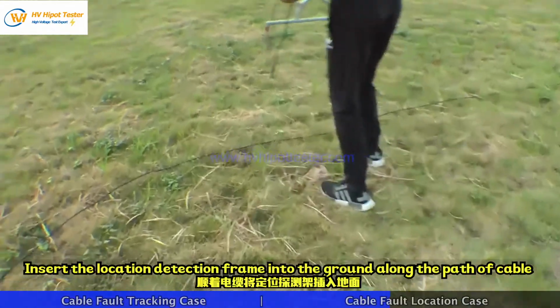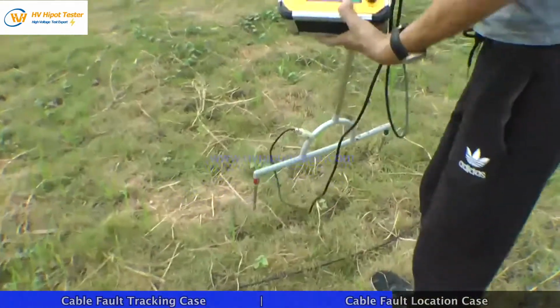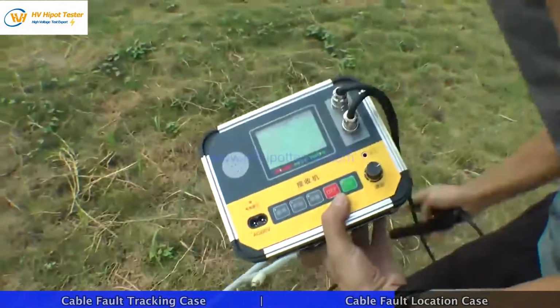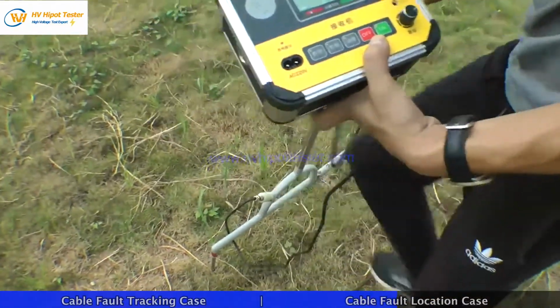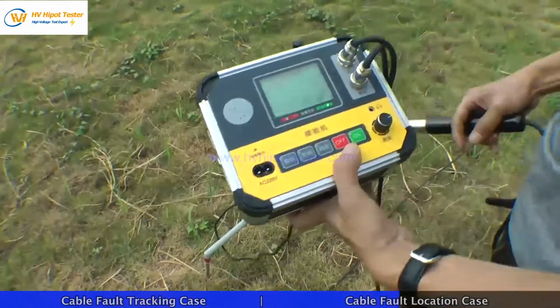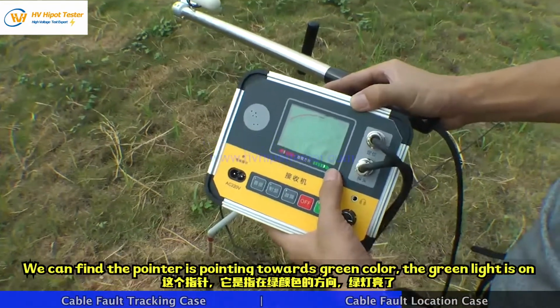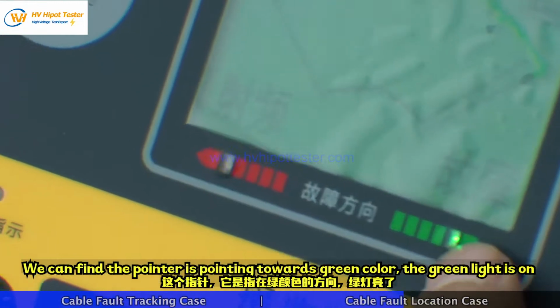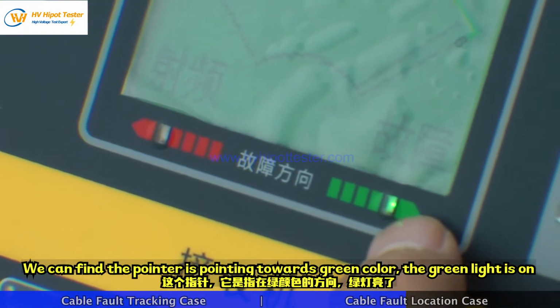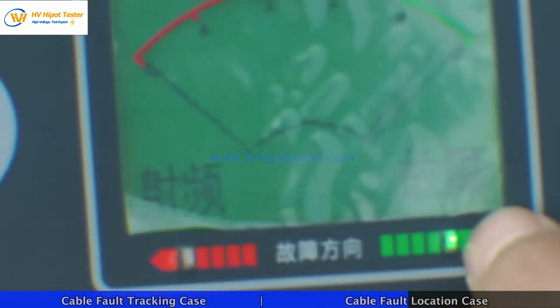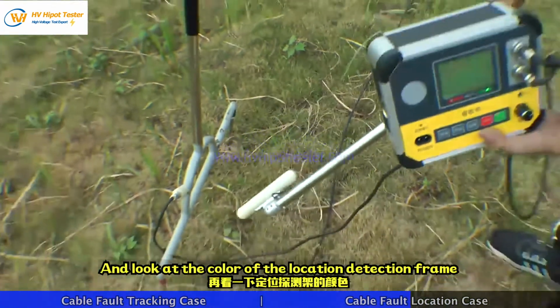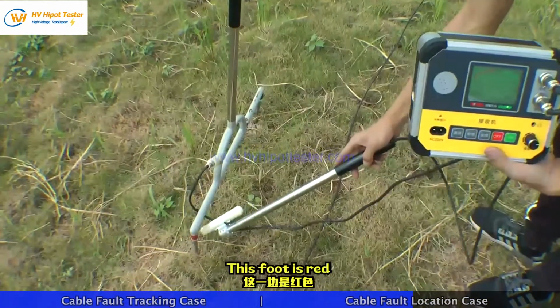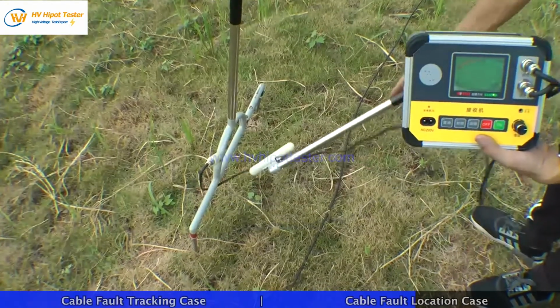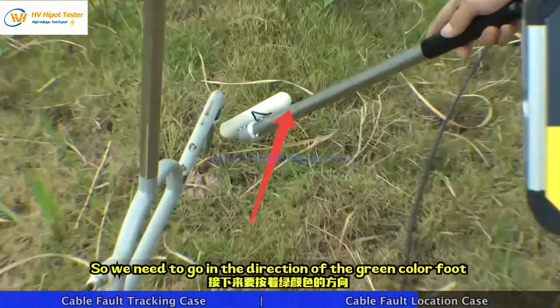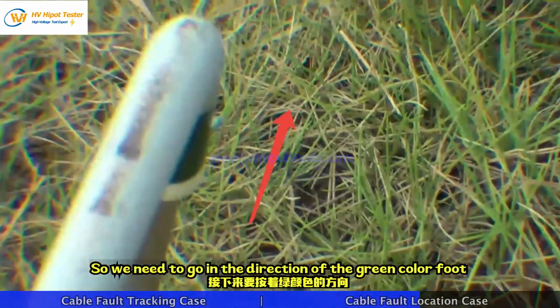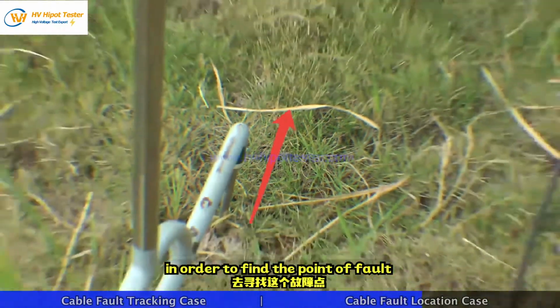Insert the location detection frame into the ground along the path of cable. We can find the pointer is pointing towards green color, the green light is on. And look at the color of the location detection frame. This foot is red. This foot is green, so we need to go in the direction of the green color foot in order to find the point of fault.